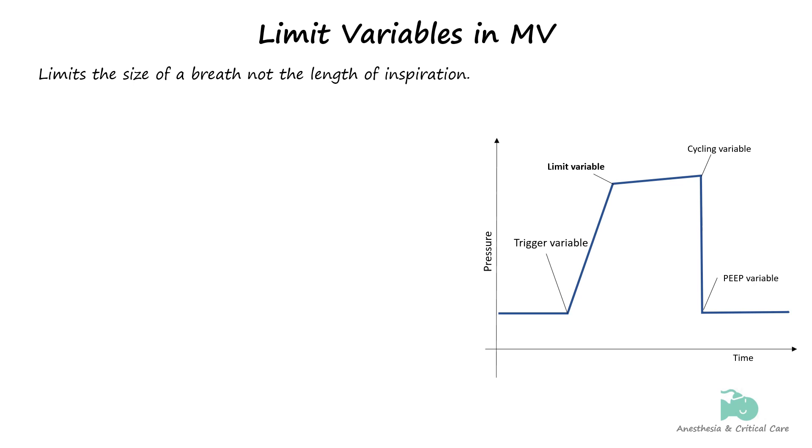The limit variable is a setting which constrains or limits the parameters of a mechanical breath like pressure, flow, and volume during the inspiratory phase. Limits are set to make sure all the other variables don't go out of control in the process of achieving the control variable.